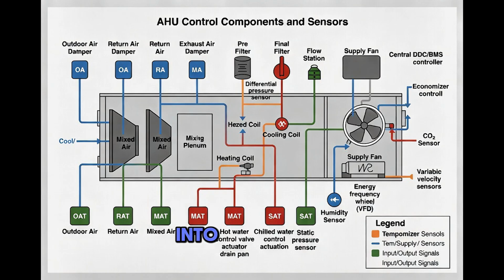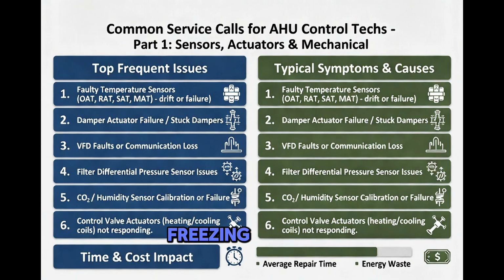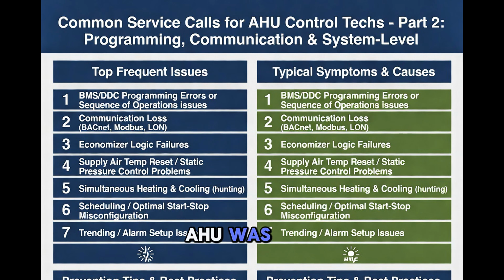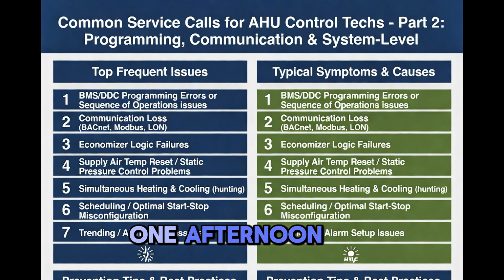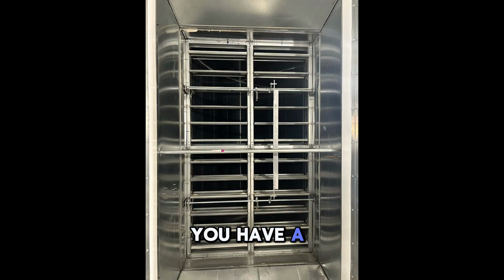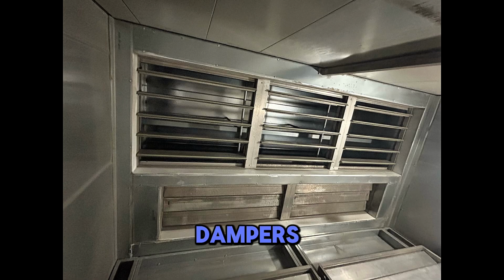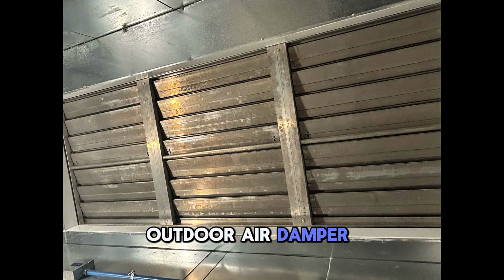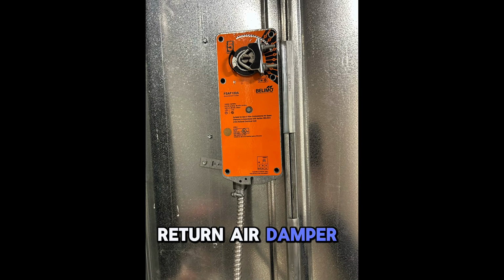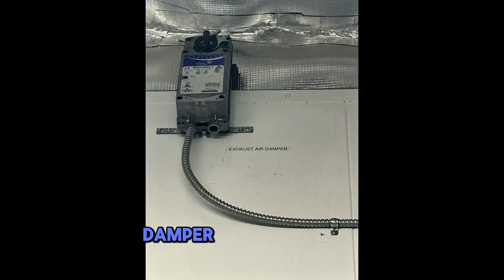I once walked into an office building where tenants were freezing on one side and roasting on the other. Turns out the AHU was the culprit. Fixing it took one afternoon and stopped hundreds of complaints. Right at the entrance, you have a mixing section with 3 sets of dampers. You have the outdoor air damper, return air damper, and the exhaust damper.